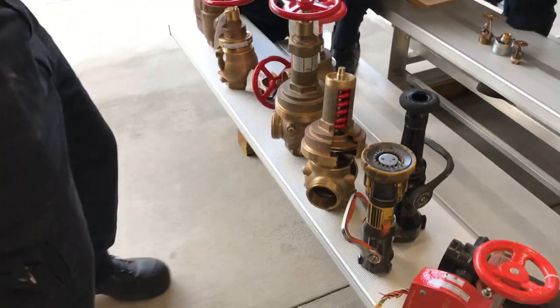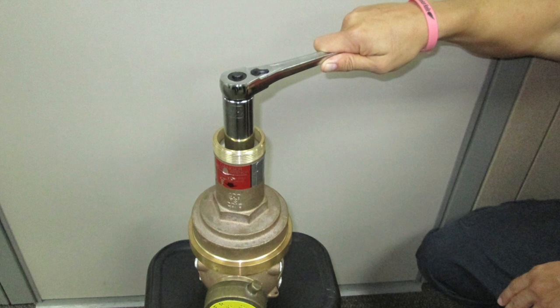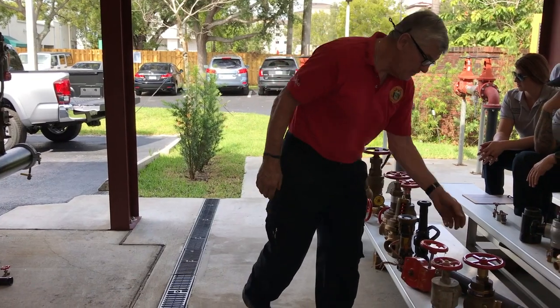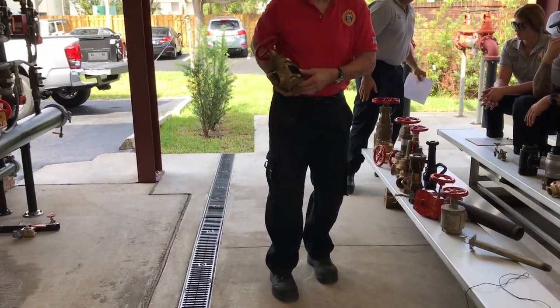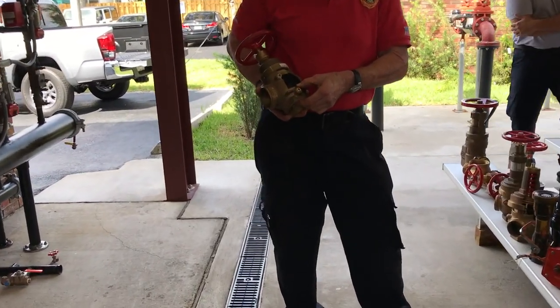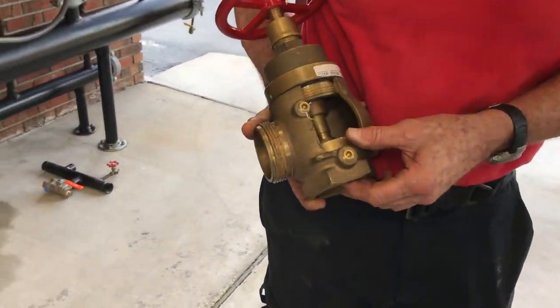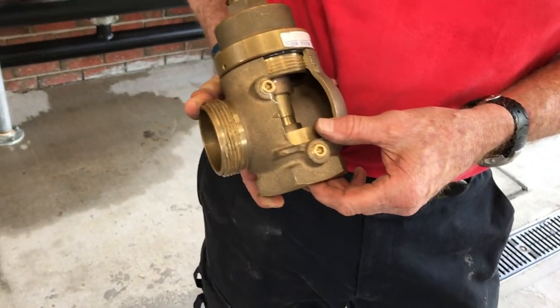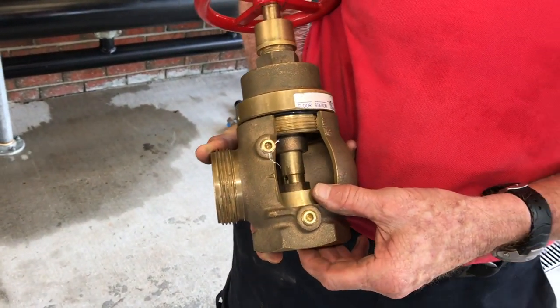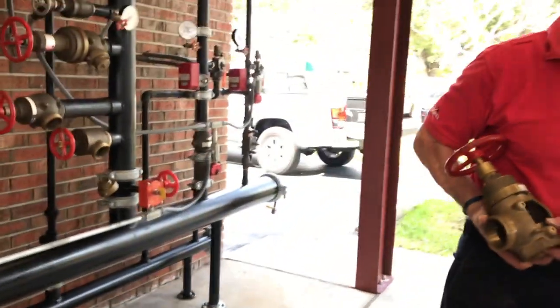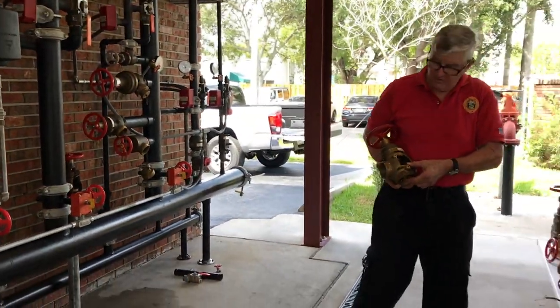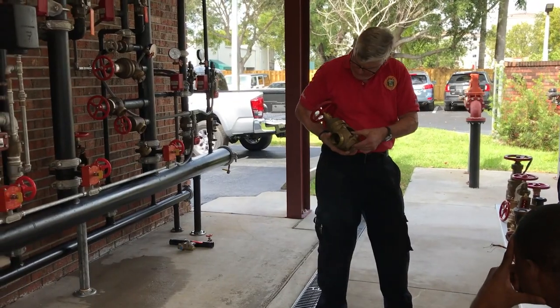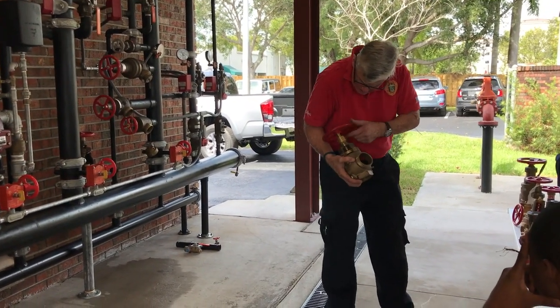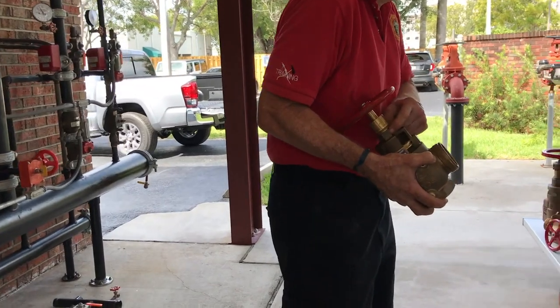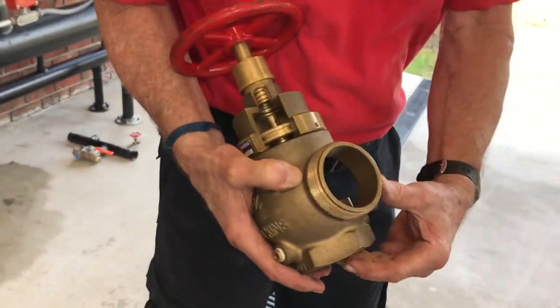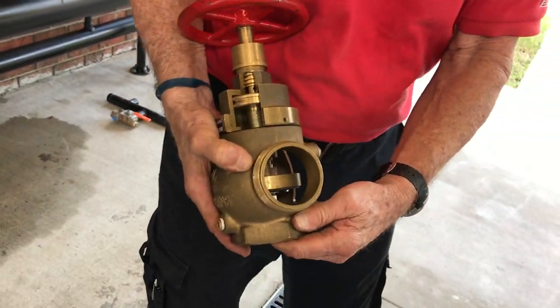Now, we can see why we have to test these devices in compliance with NFPA 25, which is the standard for testing water-based fire suppression systems. We have moving components. In fact, in this case, can you see that the hand wheel is not even mechanically connected to the piston and plunger assembly?